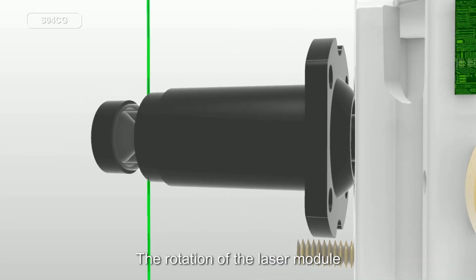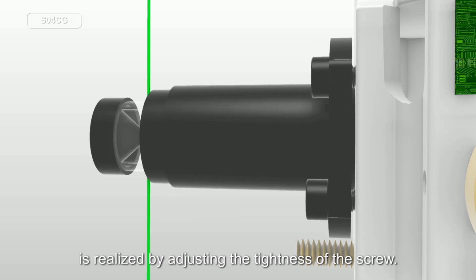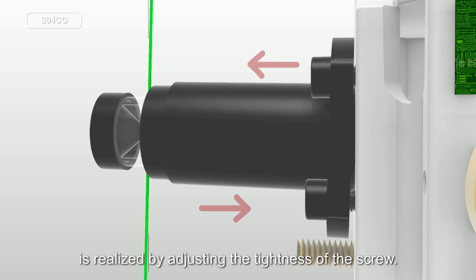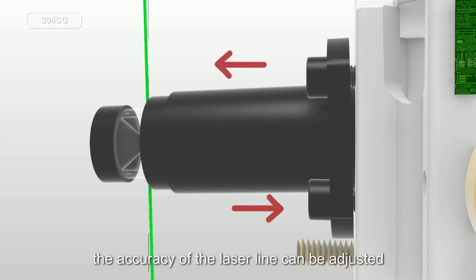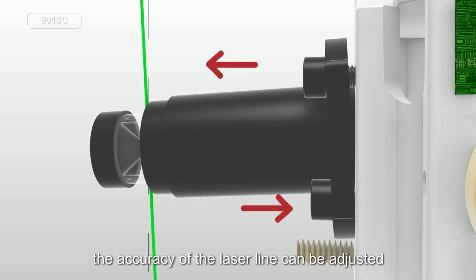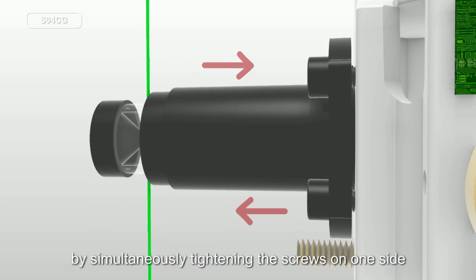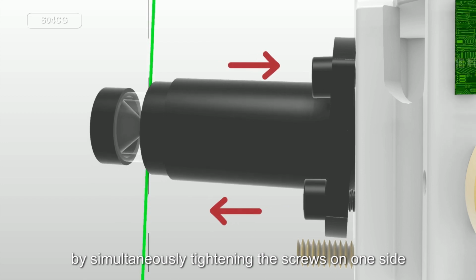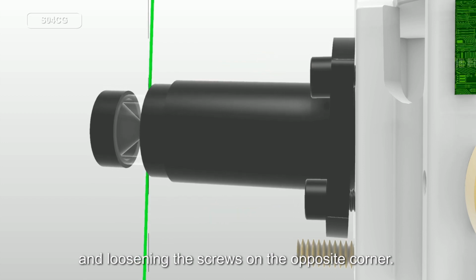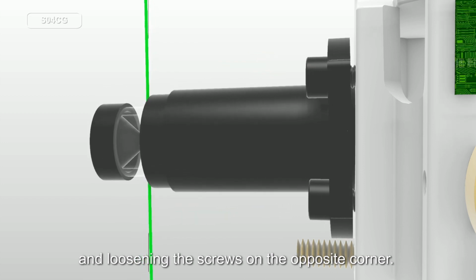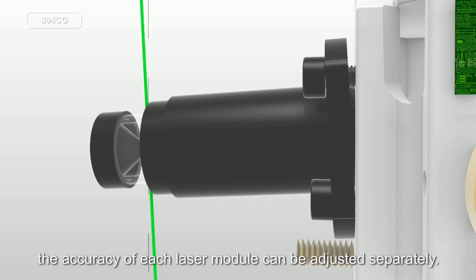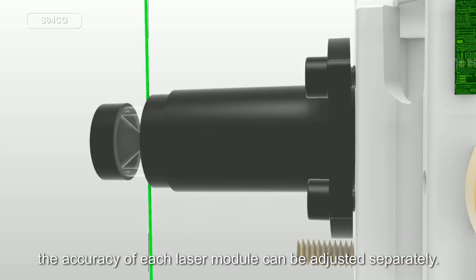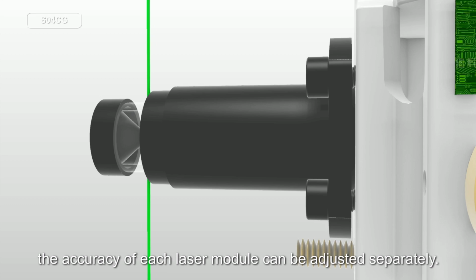The rotation of the laser module is realized by adjusting the tightness of the screw. For example, the accuracy of the laser line can be adjusted by simultaneously tightening the screws on one side and loosening the screws on the opposite corner. Through this principle, the accuracy of each laser module can be adjusted separately.